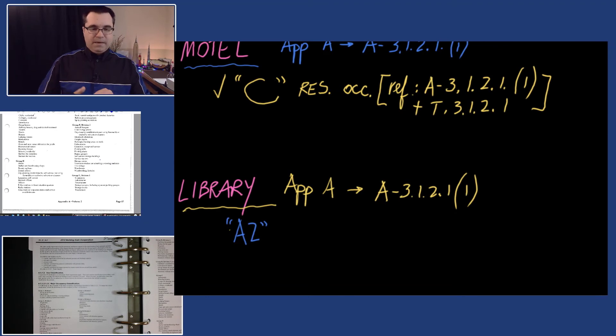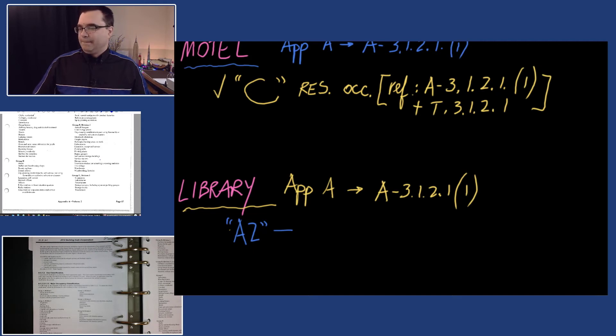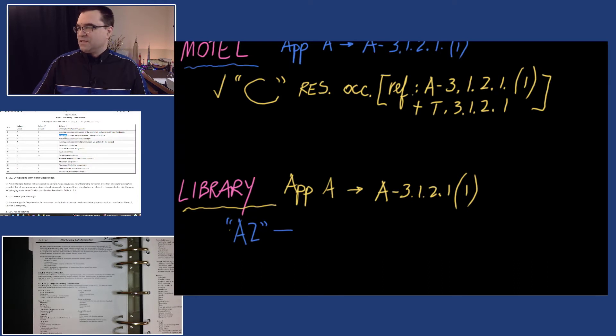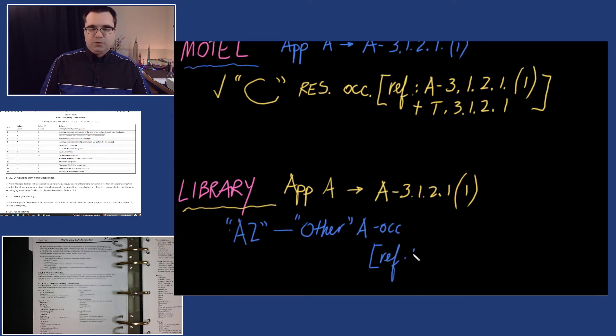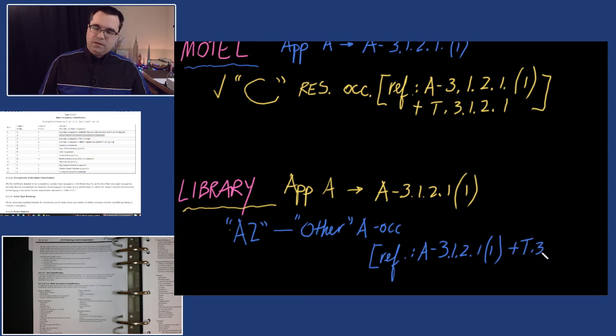So the only choice we have is A2. If we want to be thorough, Table 3.1.2.1 describes A2 as 'assembly occupancies not elsewhere classified in Group A' — I'll call these the 'other A occupancies.' For reference: A 3.1.2.1.1 plus Table 3.1.2.1. And again, don't forget we always start with the appendix.